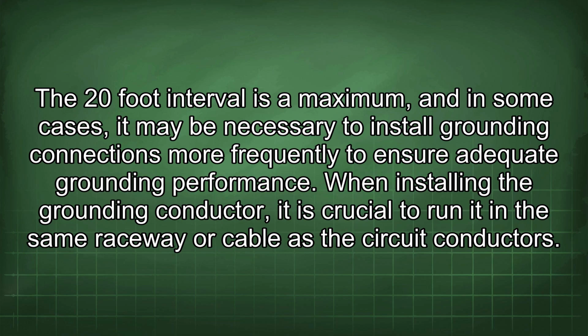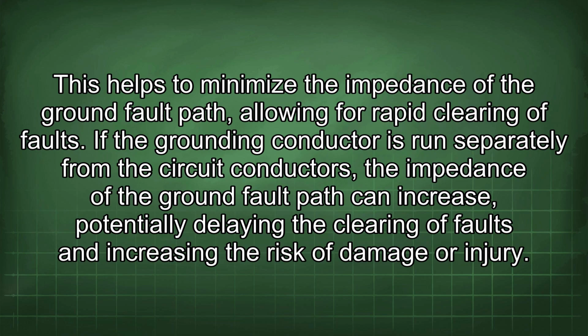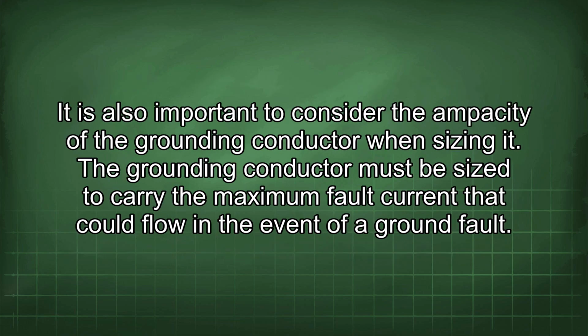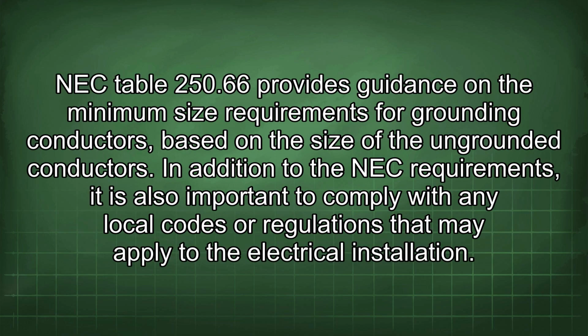When installing the grounding conductor, it is crucial to run it in the same raceway or cable as the circuit conductors. This helps to minimize the impedance of the ground fault path, allowing for rapid clearing of faults. If the grounding conductor is run separately from the circuit conductors, the impedance of the ground fault path can increase, potentially delaying the clearing of faults and increasing the risk of damage or injury. It is also important to consider the ampacity of the grounding conductor when sizing it. The grounding conductor must be sized to carry the maximum fault current that could flow in the event of a ground fault.